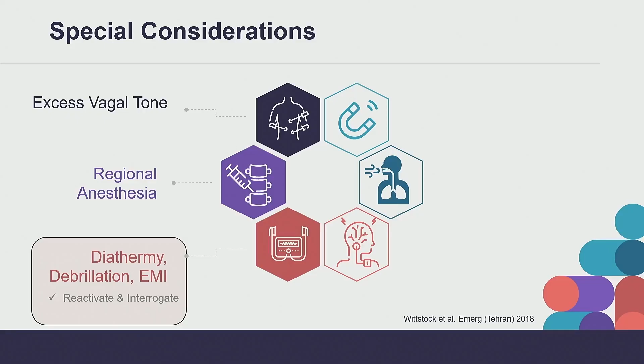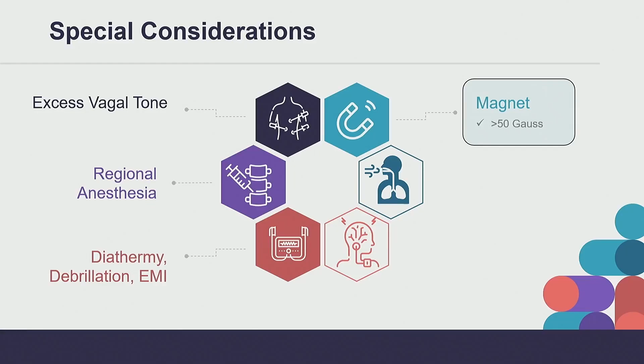If the VNS is not formally deactivated, or if the decision is made to keep the device on, a magnet should be readily available to place and to urgently deactivate the device if there's any complications. Any magnet greater than 50 Gauss in strength may be used, and the typical pacemaker or ICD magnet that we usually have is actually 90 Gauss, so that would be sufficient.